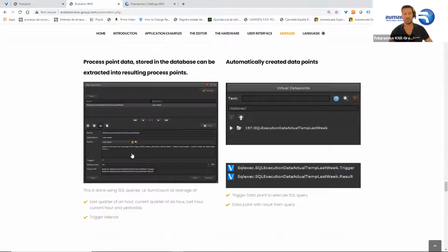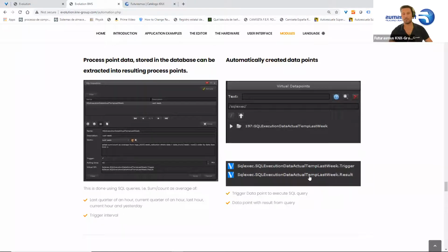You set up which value you want to use, and you can compare the last quarter of an hour, current quarter, last hour, current hour, yesterday, whatever. You set up what information you want, and it will then write this information in a process point. This process point is updated every 60 minutes, but if you want it shorter or done by a trigger, you can just send a value on the trigger, and it will send you a resulting value in the process point.